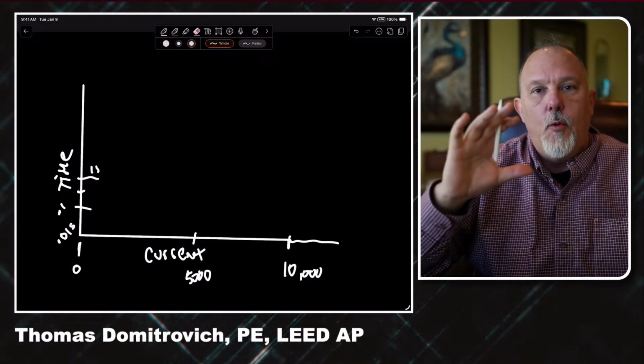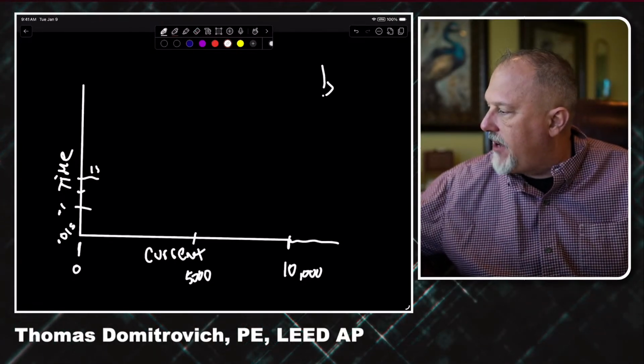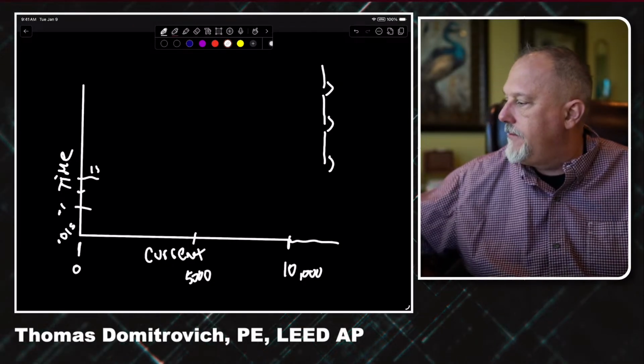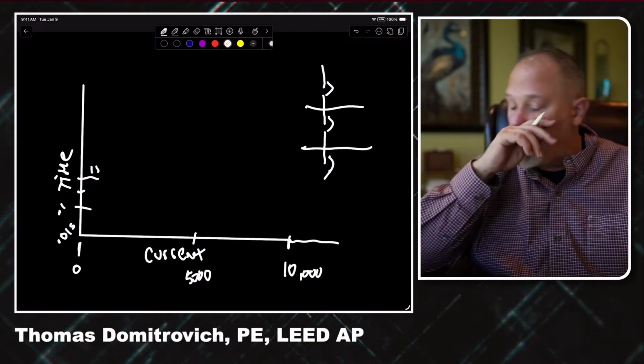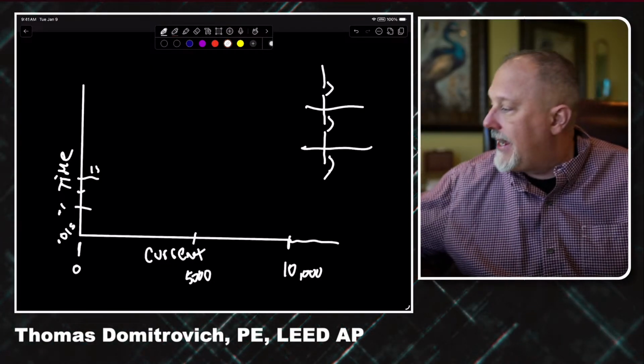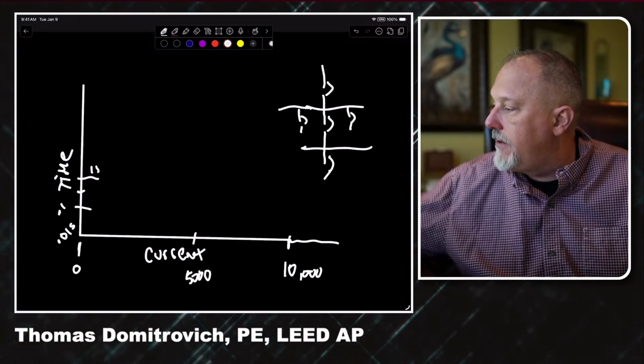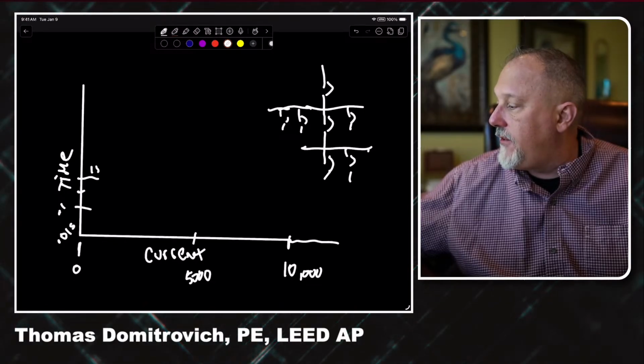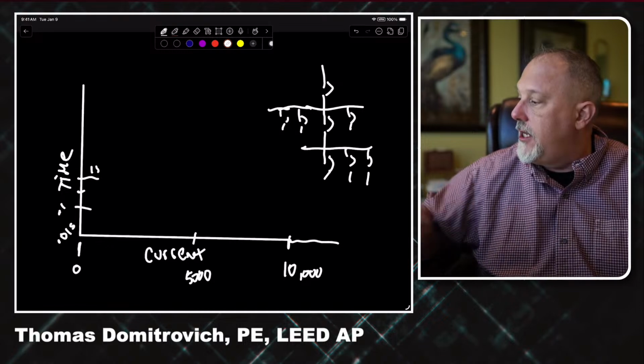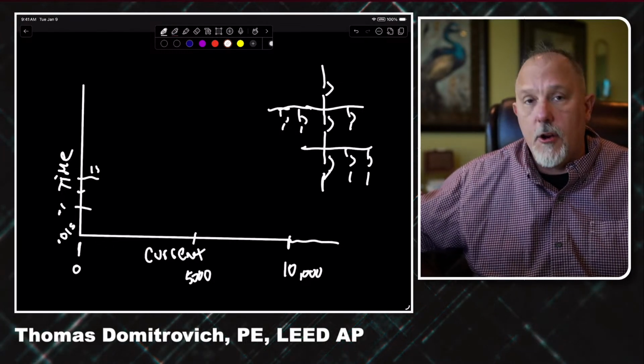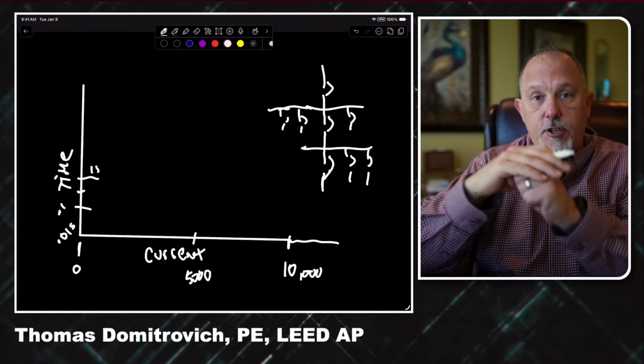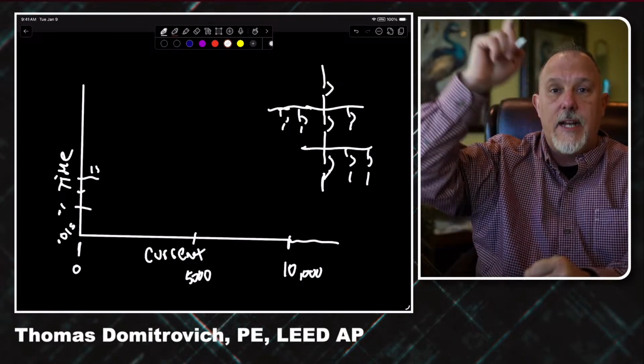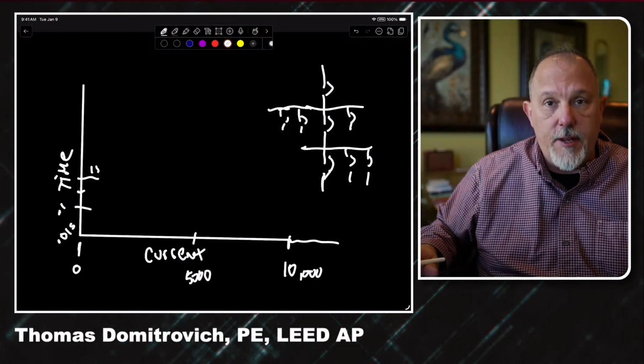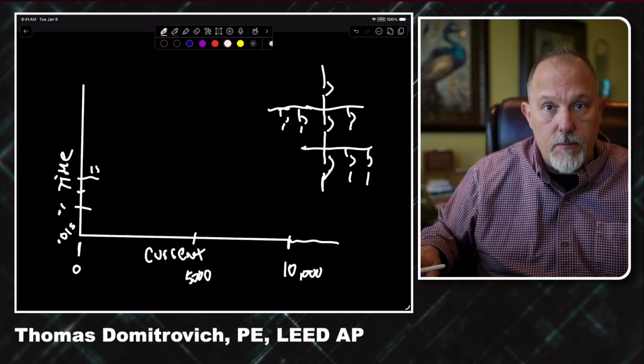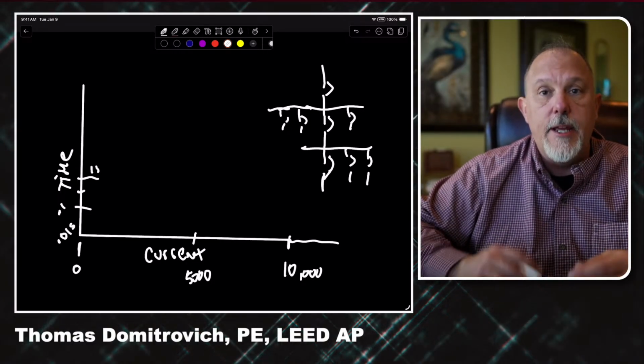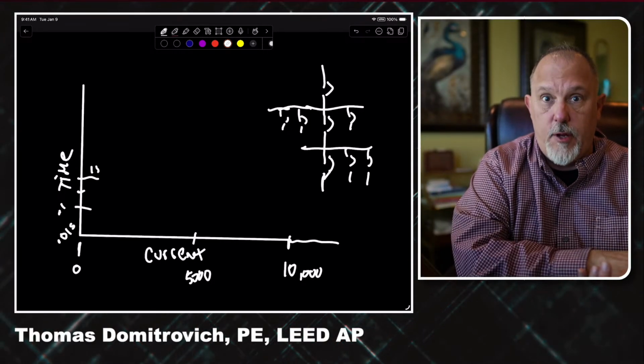All right, so when we draw a diagram, let's say I drew a diagram. I have a breaker and a breaker and a breaker. All right. And now here's the other problem. I'm showing you 3 breakers in series. Technically, at each of these panels, there's probably this going on. So don't let my drawing deceive you in thinking I've only got 3 breakers. You typically will pick the largest breaker at each panel, because if the largest breaker downstream selectively coordinates upstream, all of the smaller breakers downstream are likely to selectively coordinate as well. Because the hardest thing to do is to selectively coordinate the downstream largest breaker.